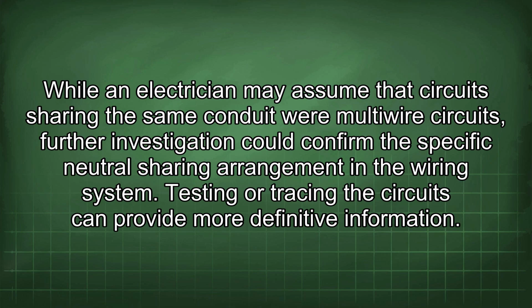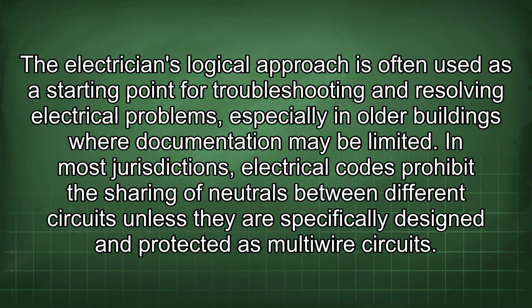Testing or tracing the circuits can provide more definitive information. The electrician's logical approach is often used as a starting point for troubleshooting and resolving electrical problems, especially in older buildings where documentation may be limited.